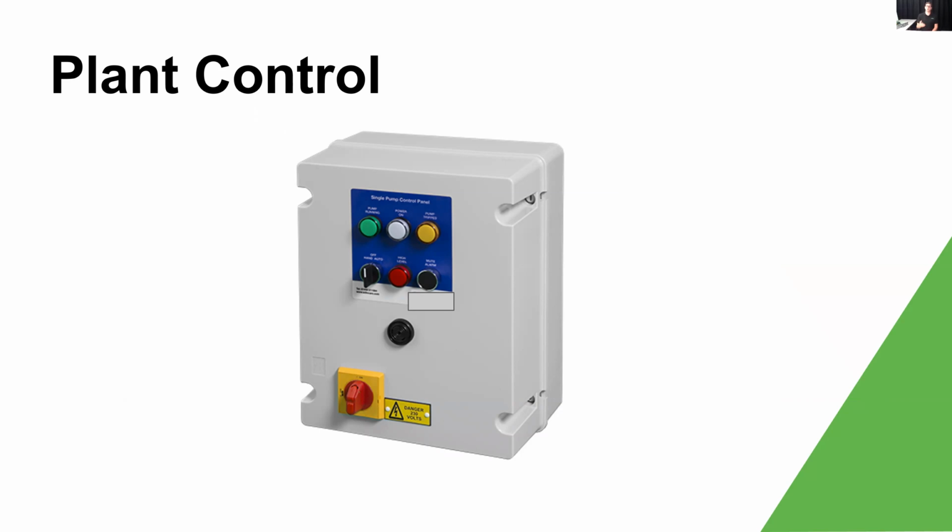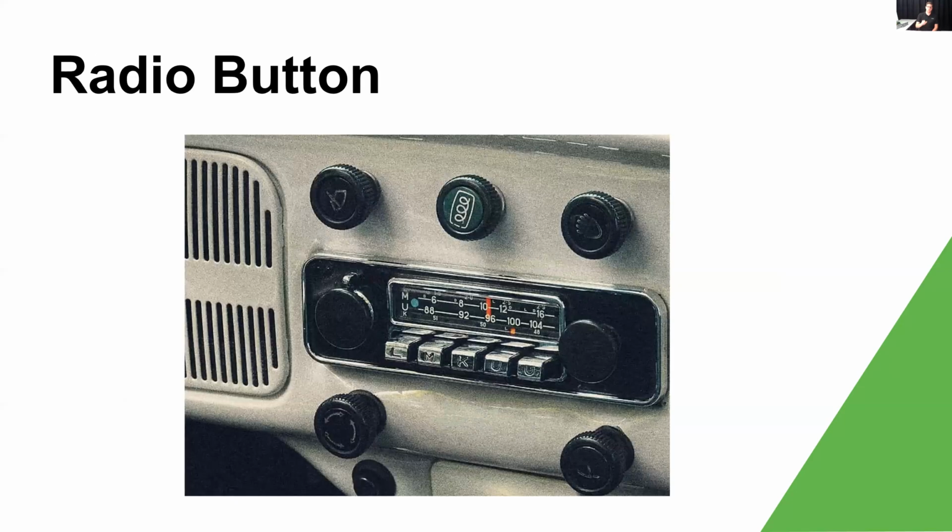Now, of course, we can do all of this within Loxone. We can do that schedule, we can do a hold on and an off, and we can then also bring in other aspects of the BMS and building control as well. And to do that, we're going to be looking in a few minutes over at this demo case here, but fundamentally there are two function blocks which make this an absolute breeze. And the main one that we're going to be using, one of my favorite function blocks, is a radio button. And a radio button works pretty much just like that picture there. The idea behind it is that only one output of a radio button can be on at any one time. So just like an old car radio, if station 3 is currently on and we press station 1, station 3's button will pop out. And that is pretty much how a radio button works as well.